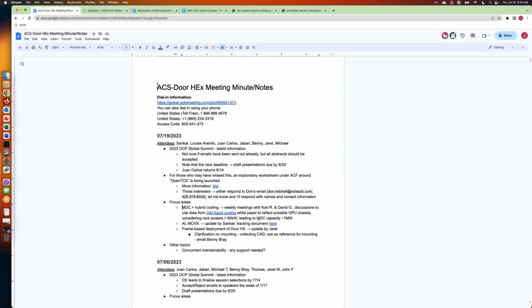Based on our initial numbers, that's leading to a modular data center capacity of 1 megawatt, which is quite high. Obviously we need to do the work to look at what this means for how much liquid needs to be brought into the modular system, and what sort of overhead pipe sizing that would look like. We can rely on the ACF white paper.